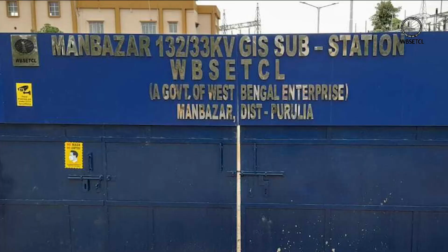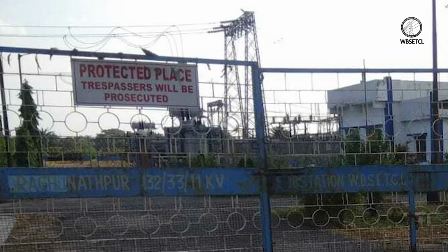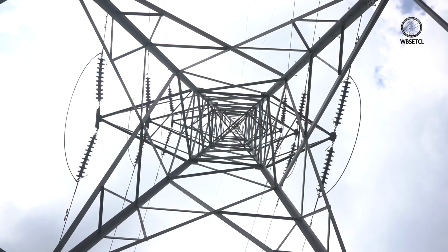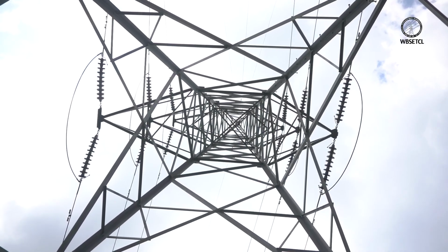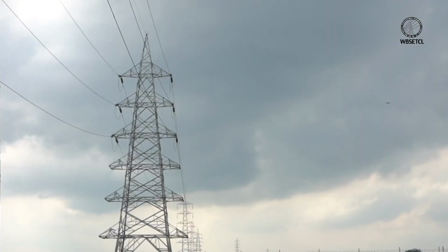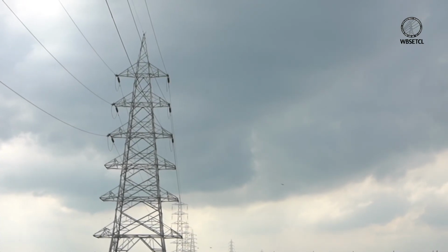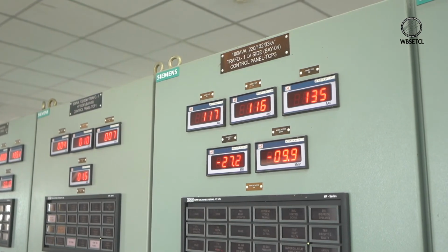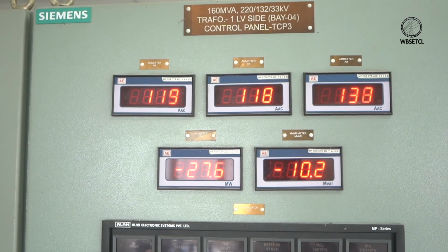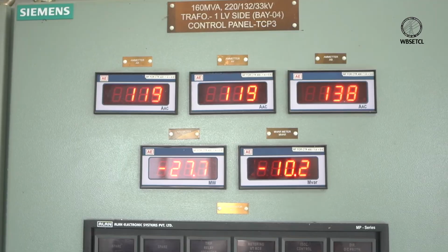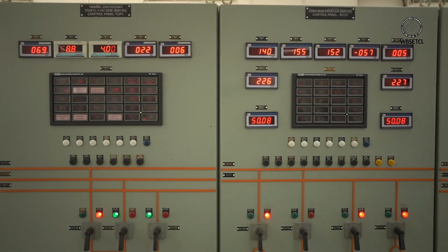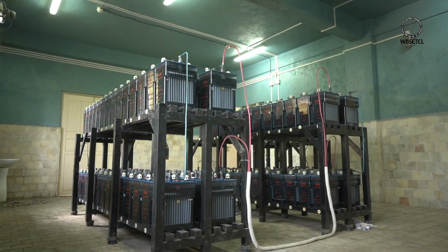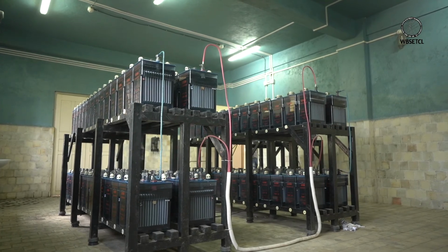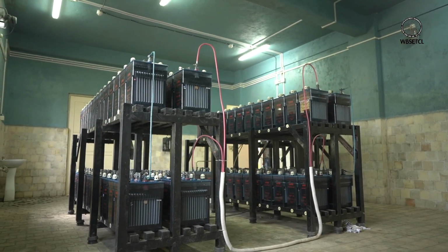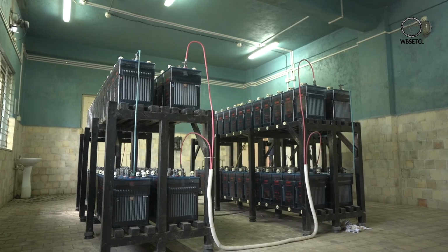kV, Manbazar 132 kV and Raghunathpur 132 kV substations, and is thus well connected with two numbers of 220 kV single circuit and three numbers of 132 kV double circuit transmission lines, thereby exercising state-of-the-art system flexibility, precise protection system and advanced safety arrangements. A separate battery room is maintained for stacking and periodic maintenance of battery banks used for the DC operated protection system.